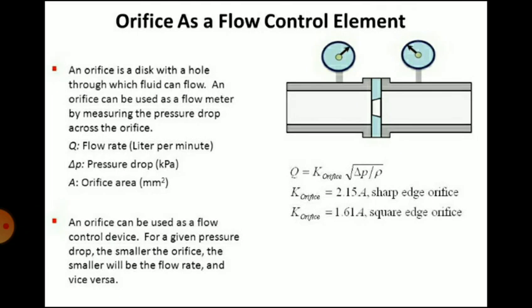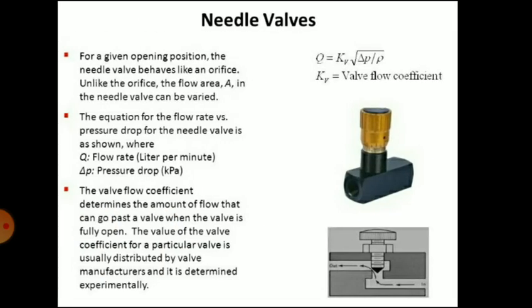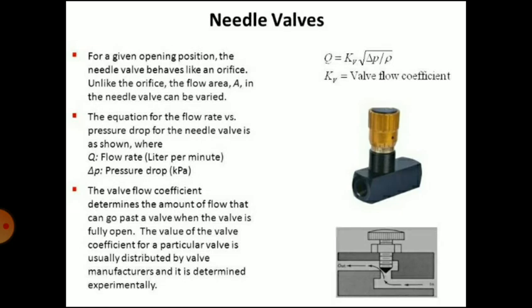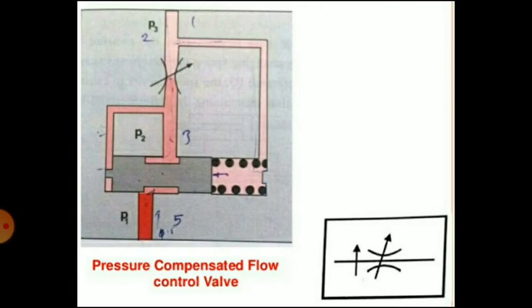The first type of non-compensating valve is the orifice as a flow control element. An orifice is a disc with a hole through which fluid can flow. An orifice can be used as a flow meter by measuring the pressure drop across it, or as a flow control valve for a given pressure drop. The smaller the orifice, the smaller will be the flow rate, and vice versa. For a given opening position, the needle valve behaves like an orifice, but unlike the orifice, the flow area A in the needle valve can be varied.